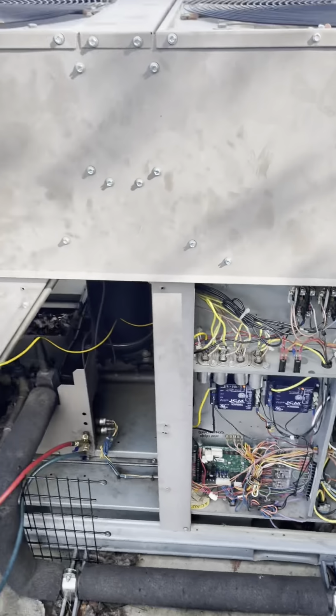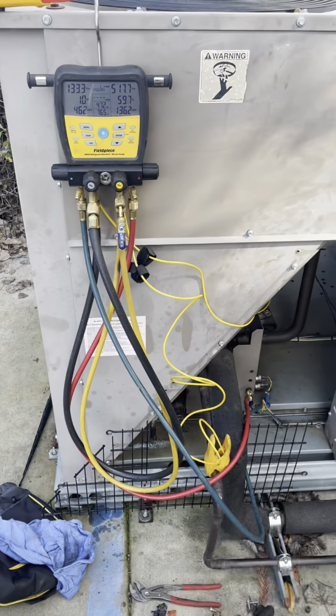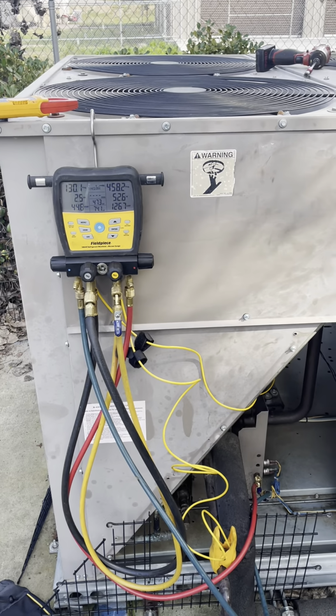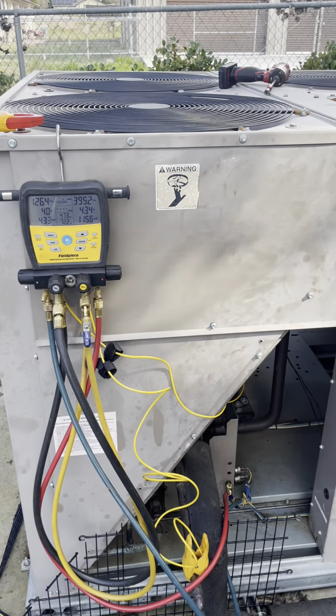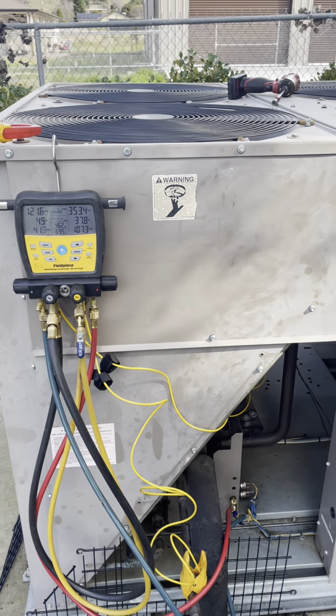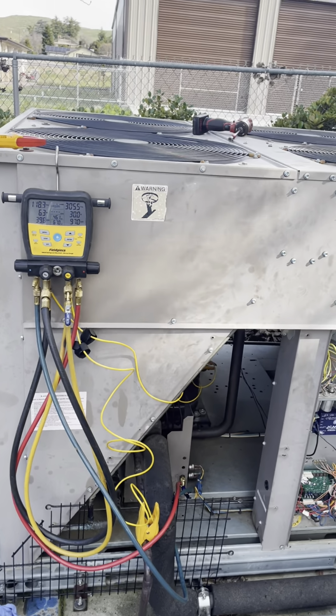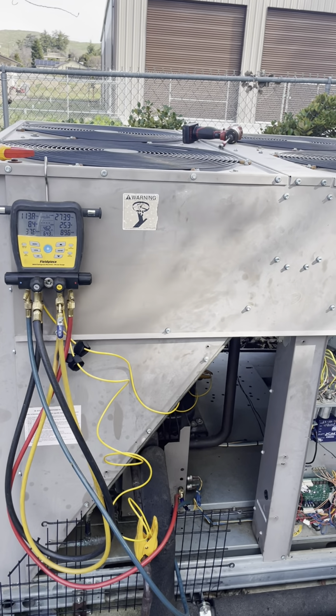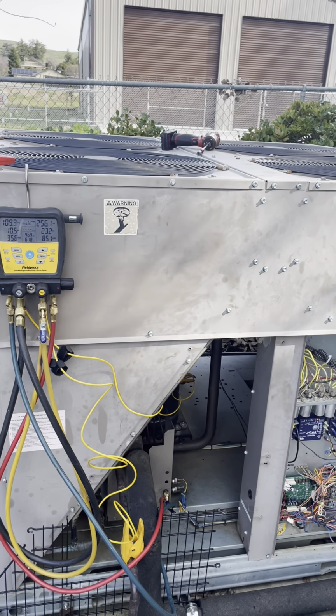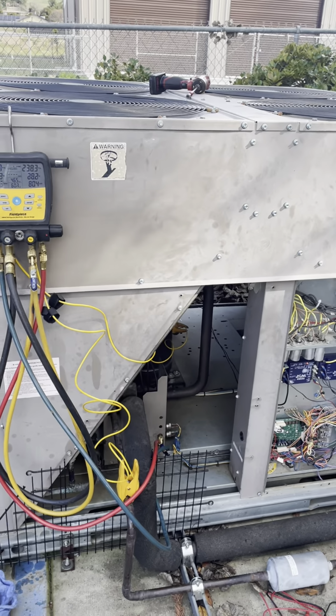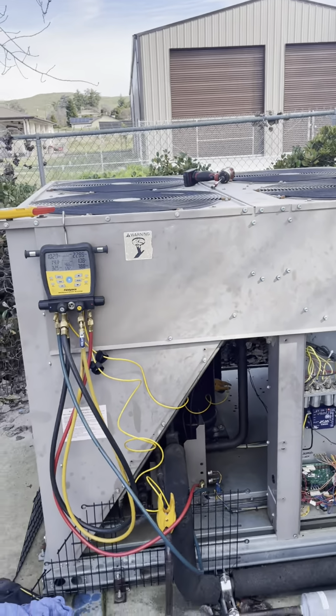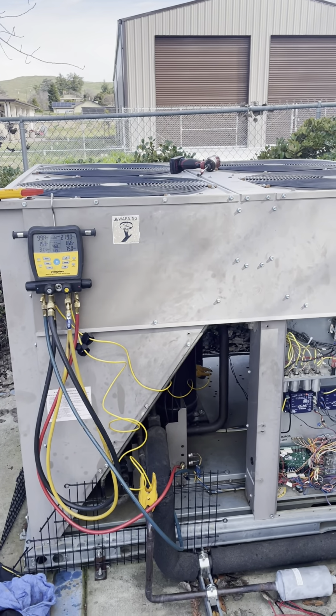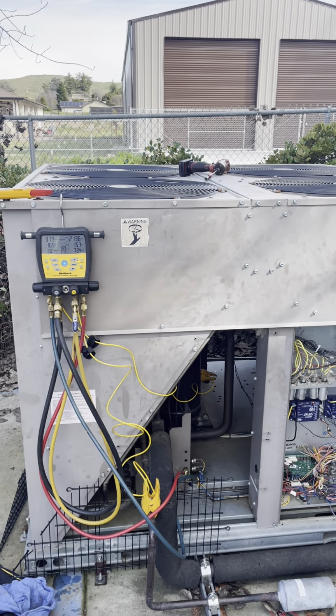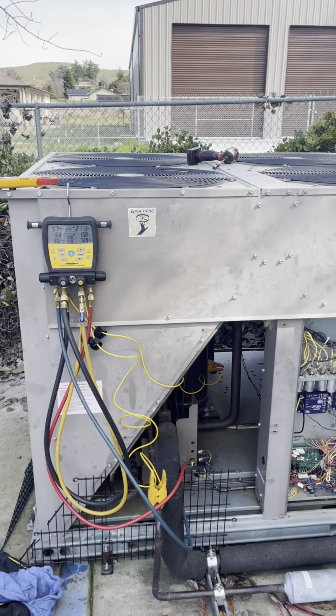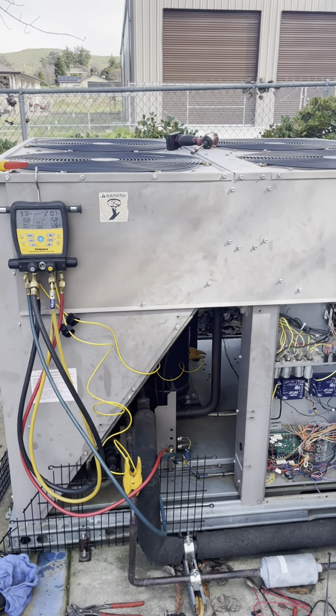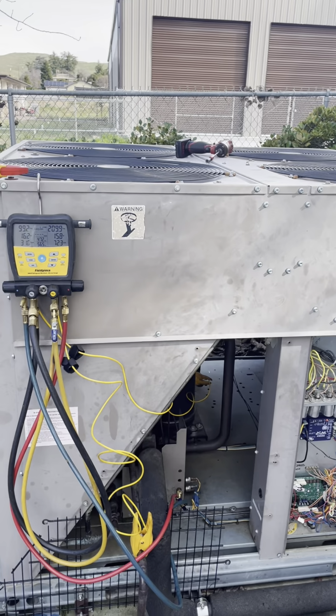But what was happening is when the thermistor was on the liquid line, the temperature swing was so drastic that it wouldn't register in time. Our head pressure would climb up to 500 psi, and my liquid line temperature would still be around 65, 70 degrees. It took a little bit for it to register that the pressure was that high, because it's not reading pressure, it's reading temperature. So there is so much of a lag. The ambient temperature here is cool at this time of year, about 45, 50 degrees. So once these fans ramp up, it drops that temperature real quick. But the compressor continues to run, so that pressure is able to build up, and then it builds up to too high a pressure and cuts out on a high pressure lockout.